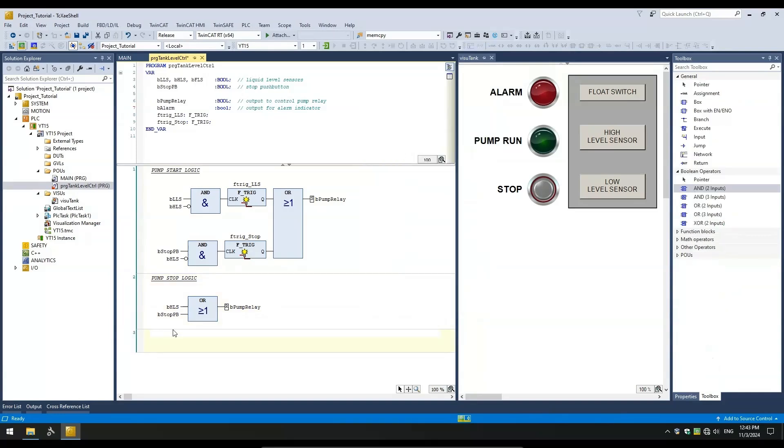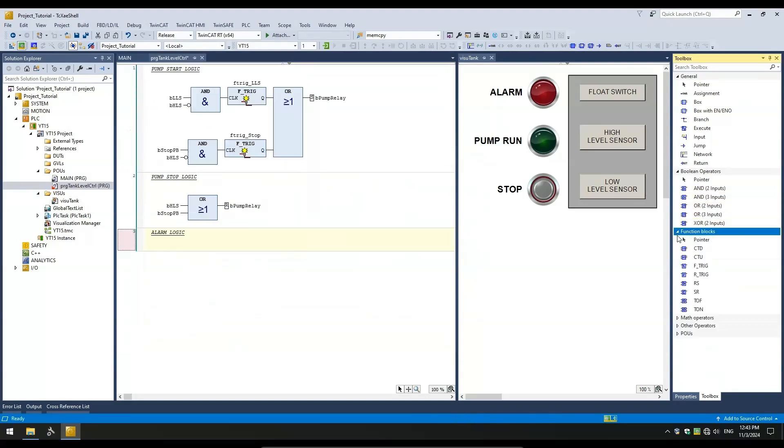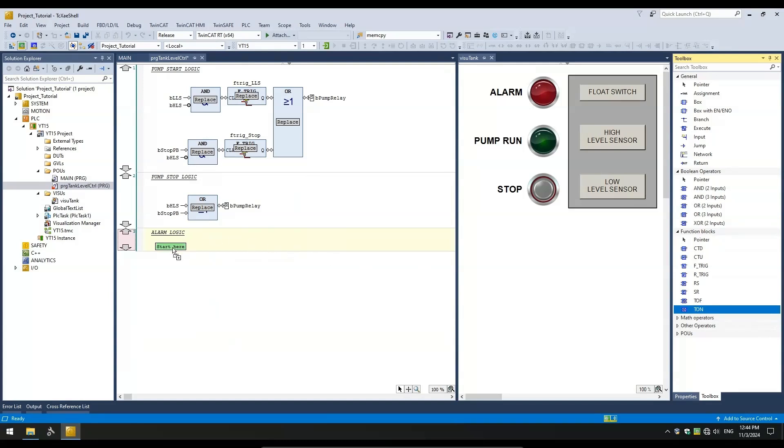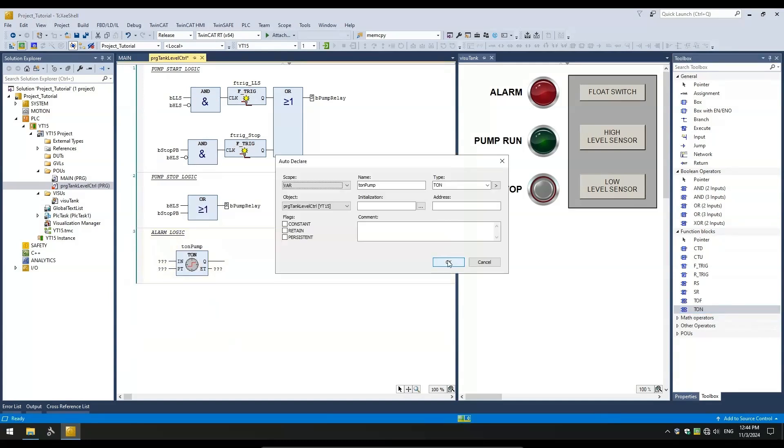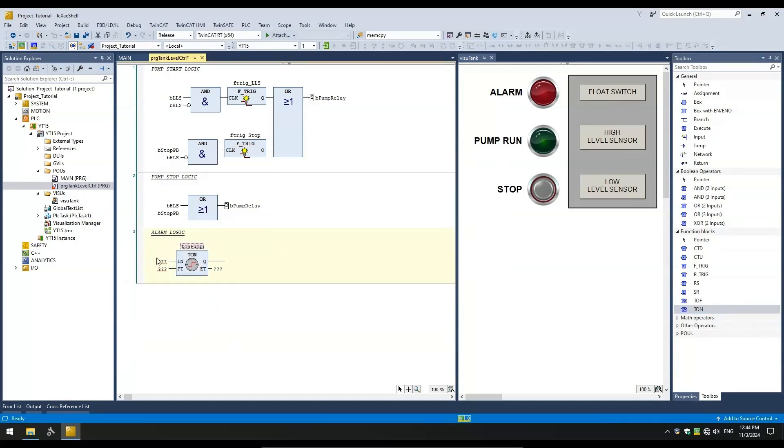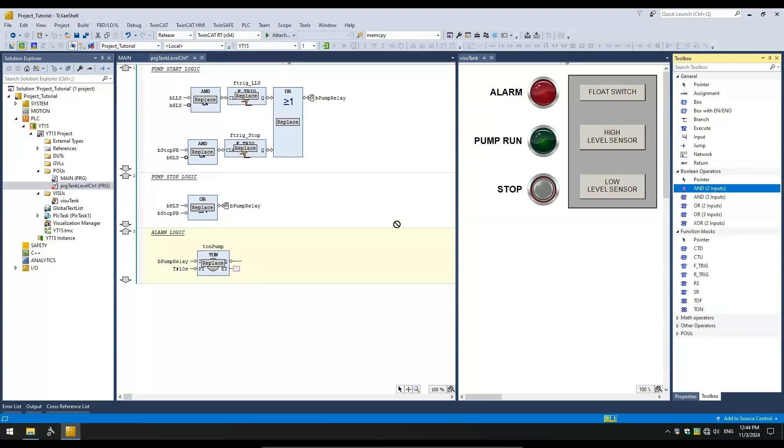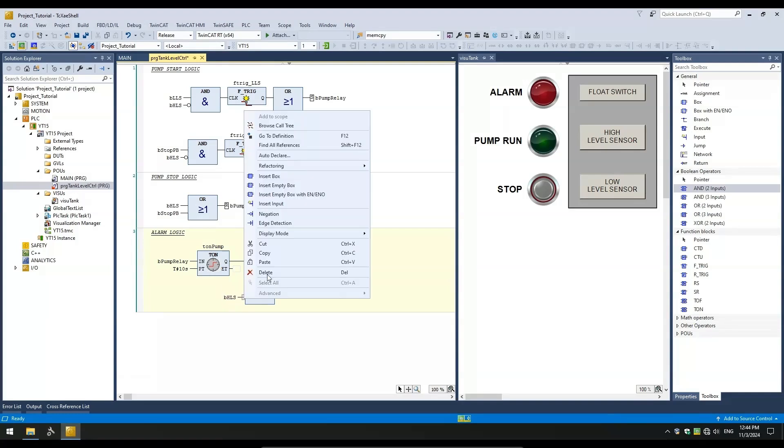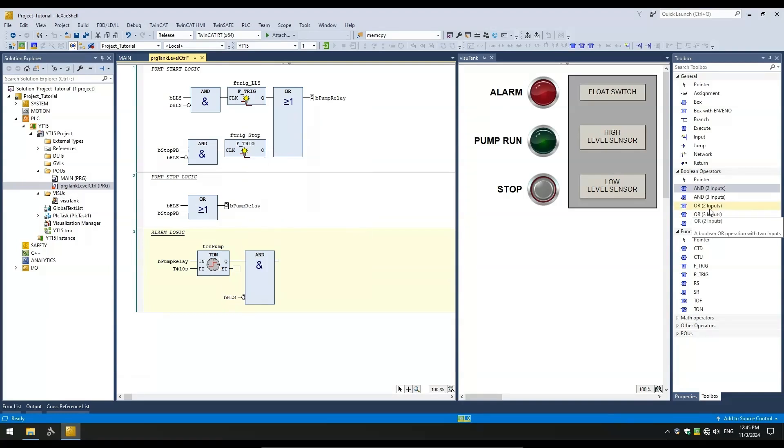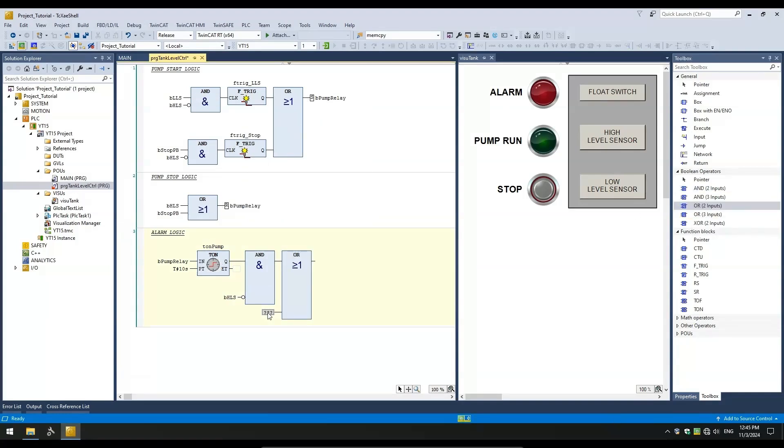Start by adding another network below and I will give it a title called alarm logic. Next, I will add a TON timer from the function blocks group in the toolbox. And call it TON pump. Its input trigger will be the start pump relay output variable. And for the preset time, I will set it to 10 seconds. Next, I will add the rest of the logic for the float switch input and the stop push button input.